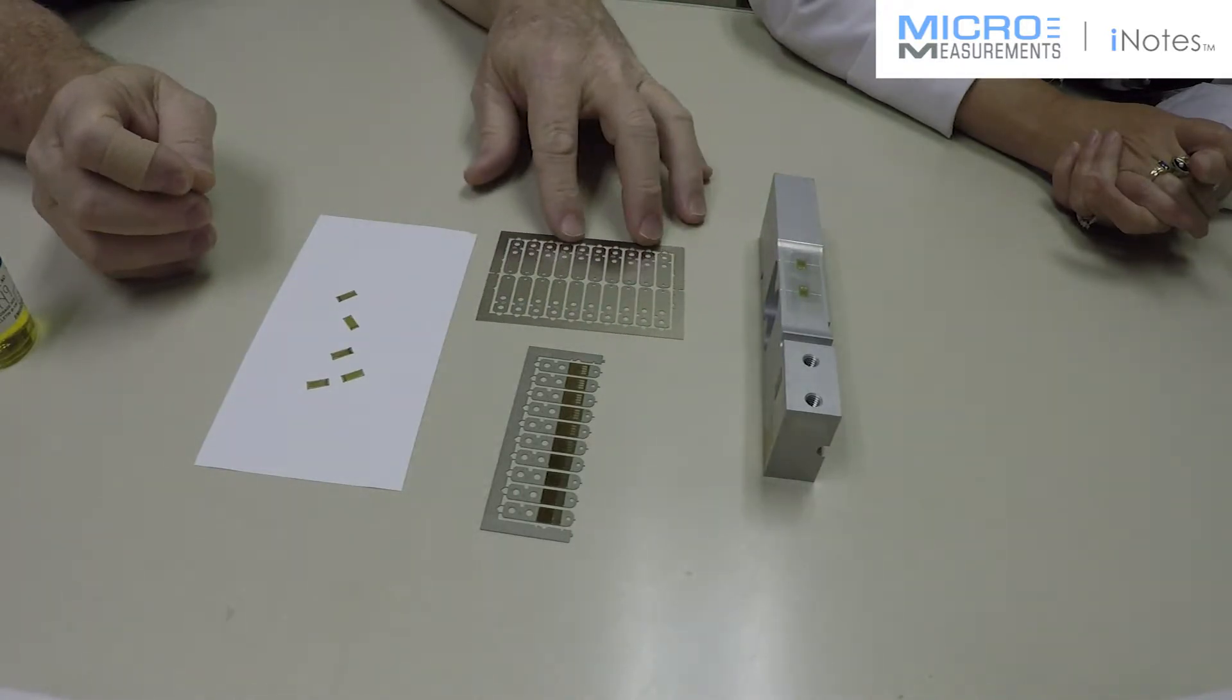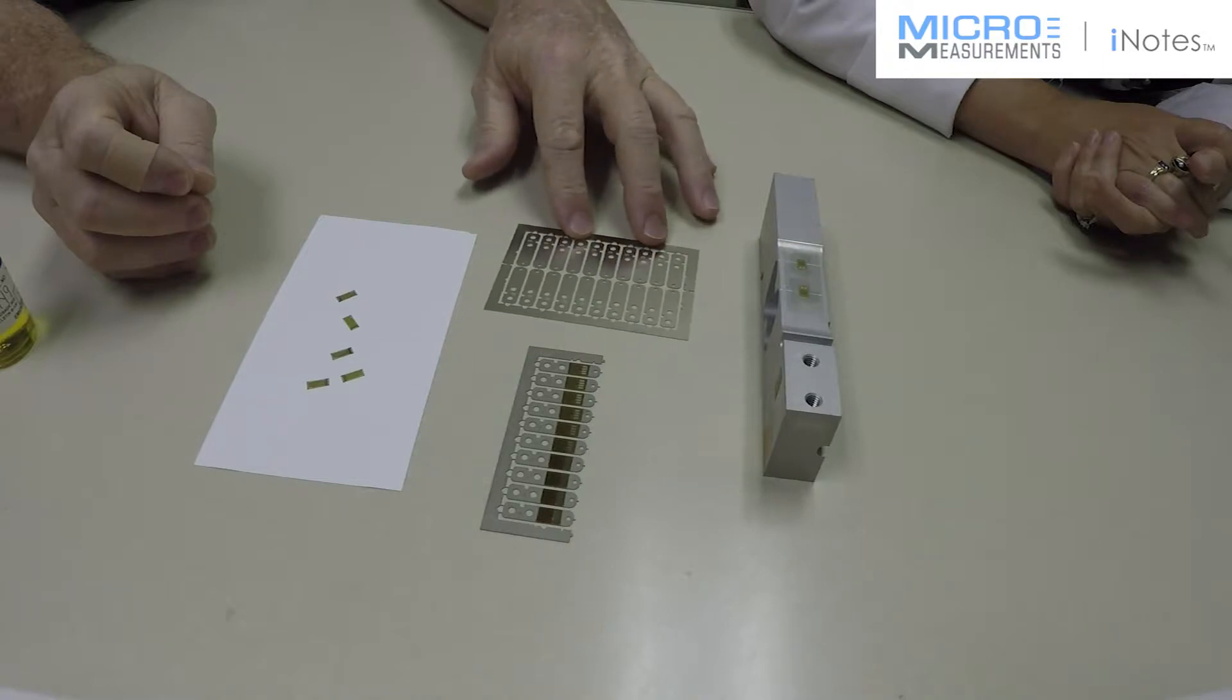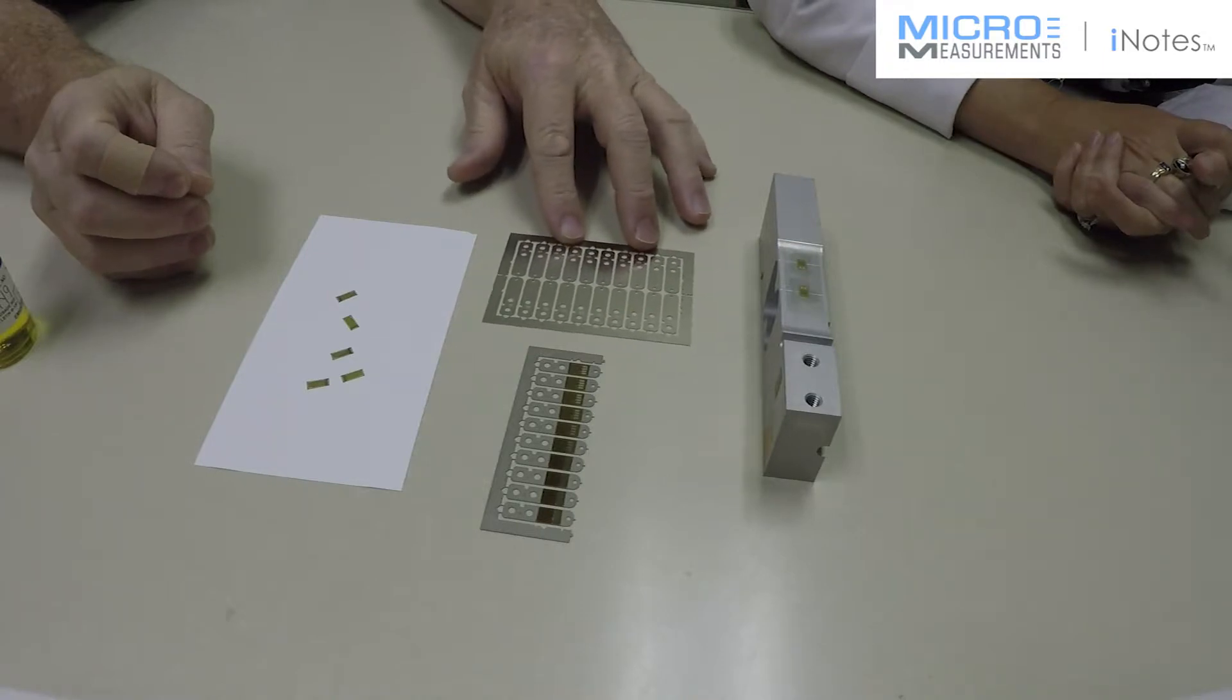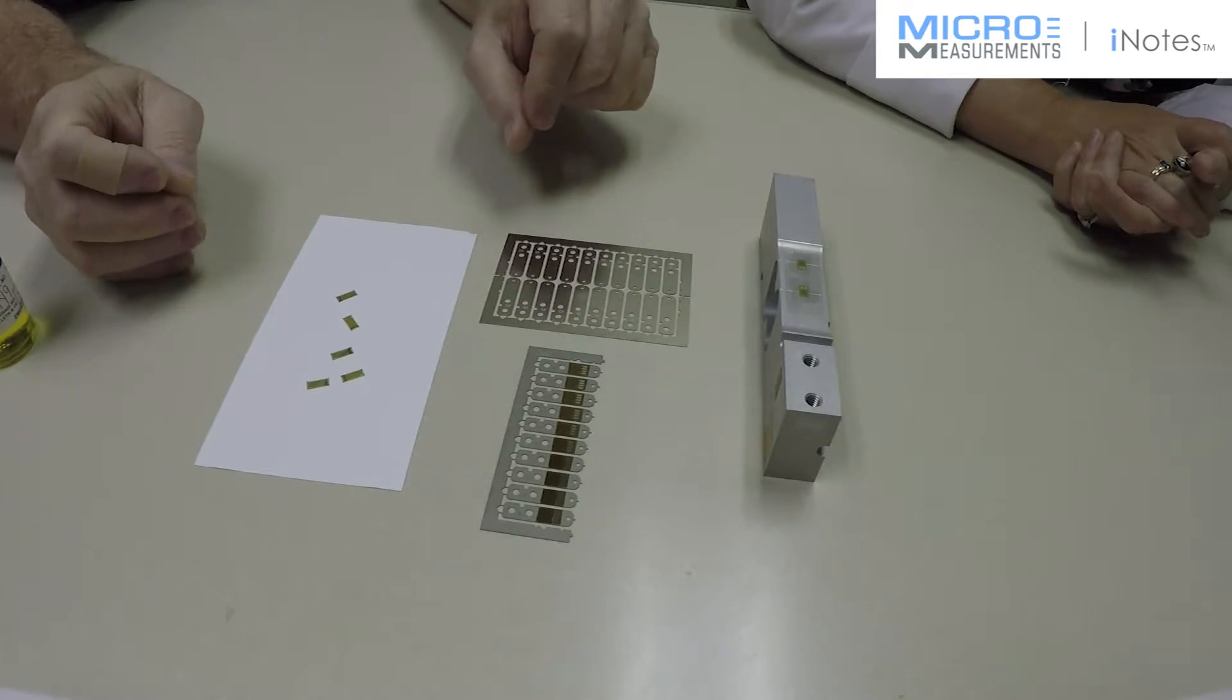and can then be placed onto the spring element. If the spring element's very thin, like these hybrid sensors, you can just tack it with a soldering iron in place, clamp it and cure it.